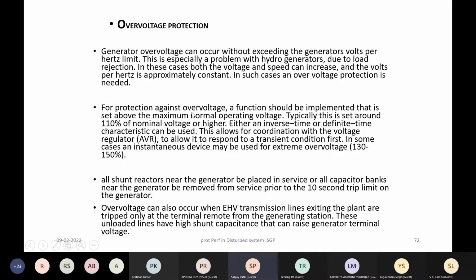Now here again, some coordination is required, or the setting change in an automatic manner should happen if you are isolated. If you are in islanded condition, then maybe the time delay should be appropriately higher, so that corrective actions for over voltage by way of switching of reactor or absorbing the excitation reactive power by the generator can bring down the voltage. So this is something which needs to be looked at.